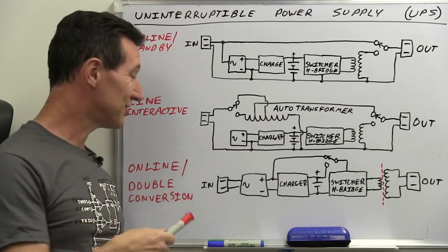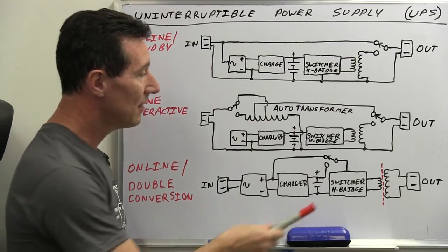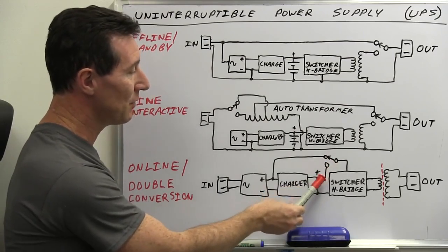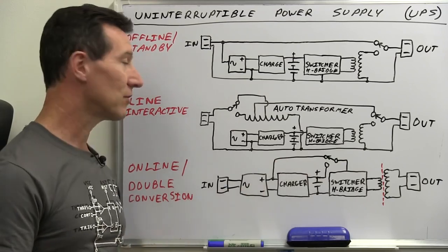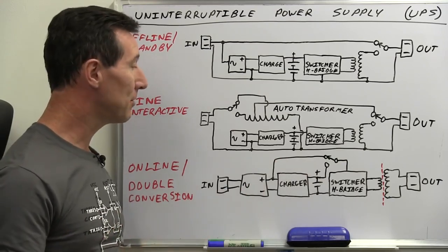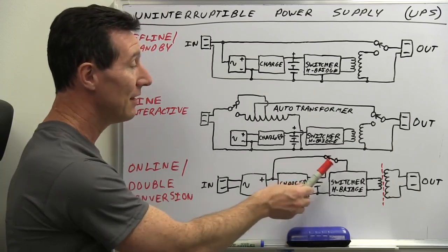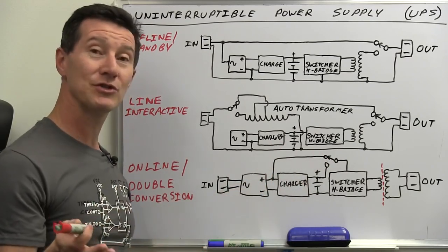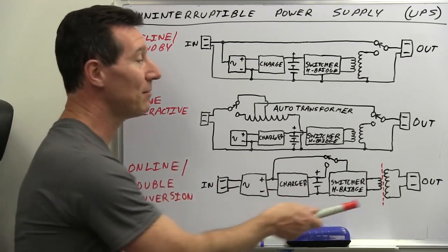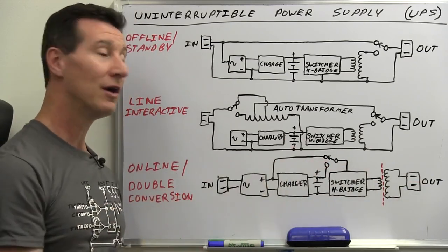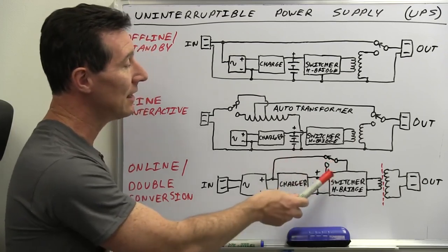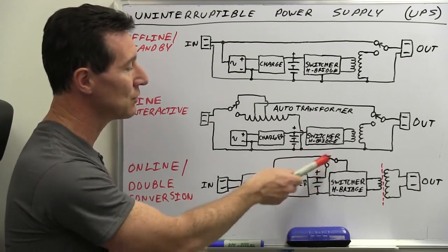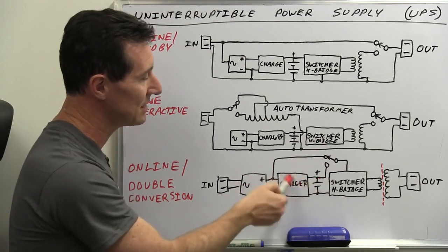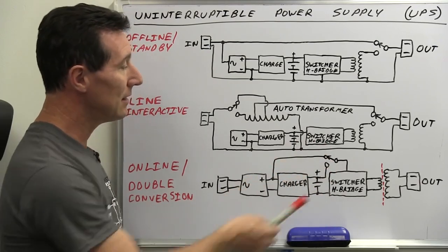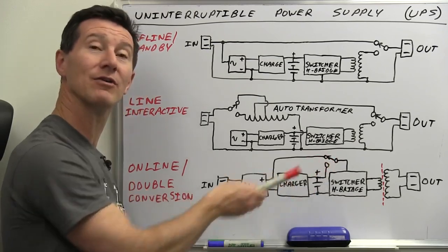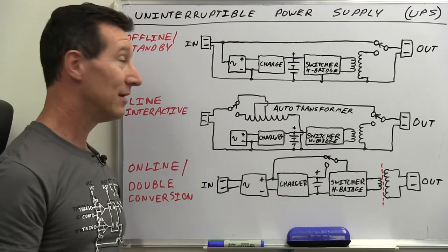But one of the disadvantages of this double conversion type is that, well, you notice that this switch down here is switching the relatively low voltage battery. For example, a 48 volt battery might be typical. They might be using 12 volts, for example. Then with lower voltage, Ohm's law still must apply, right? That means for the same amount of output power delivered to the load, you've got much higher switching currents in here. So I've shown this as a mechanical switcher relay, and the topology doesn't exactly need to be like that, but it basically means you've got very high switching currents in here that you have to switch from the battery.